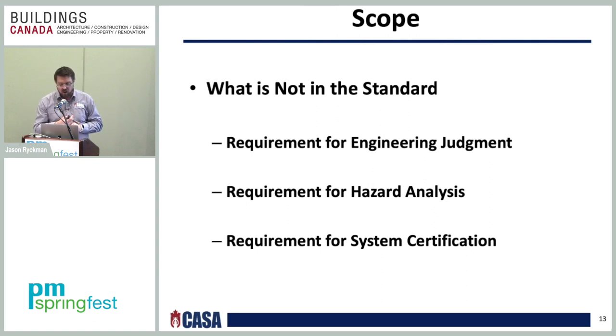In order to manage the cost of inspection while providing a reasonable degree of protection, NFPA 25 assumes that if no changes were made to the building or the hazard, and the original installation was accepted by the applicable authority having jurisdiction, then it would still be considered acceptable, okay? So if you have any change of use, you will get yourself into trouble if you do not report those changes of use. It's basically against the fire code and against the NFPA 25 document. So when you do have a change of use, please speak up and follow the proper channels to make sure that you have a proper occupancy.